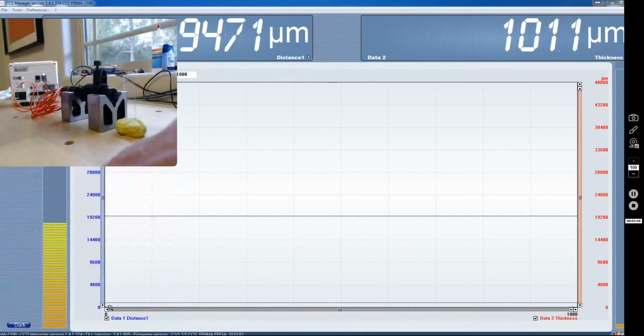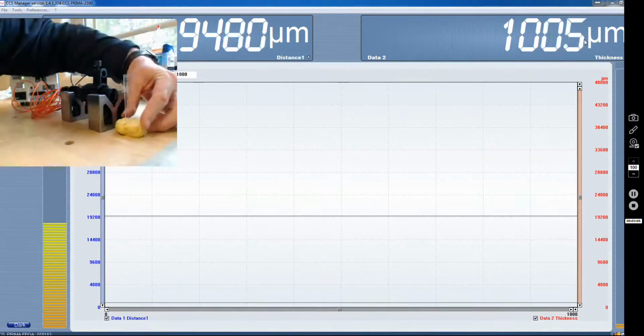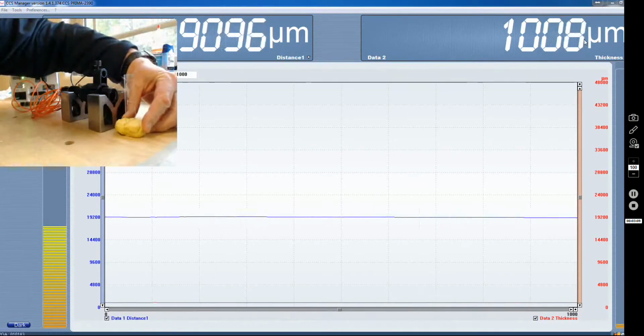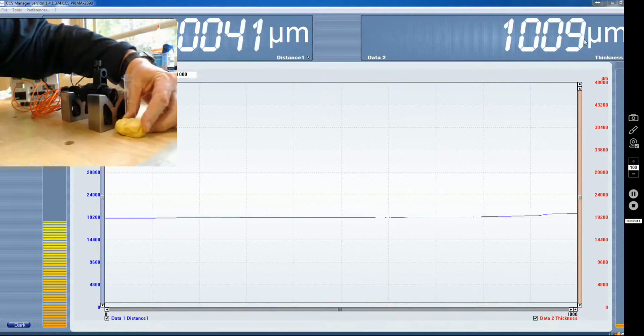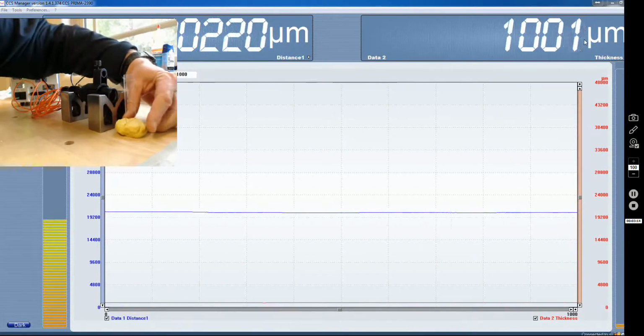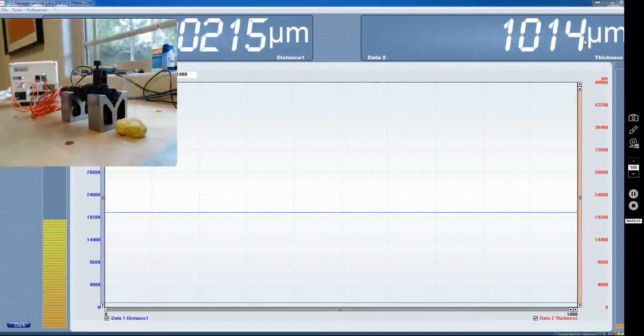So here you can see we have from 0 to 24 millimeters. Here the blue line is the front face. It tells me where the front face is, and the red is the thickness. And as you can see, we're measuring a thickness of roughly 1,000 microns or a millimeter, which is what this slide is. Microscope slides are very, very accurate, and I'm turning it a little right to left, and you can see that we are able to measure that slope. We are almost exactly on 1 millimeter, and of course we can introduce a specific index of refraction to make any corrections.